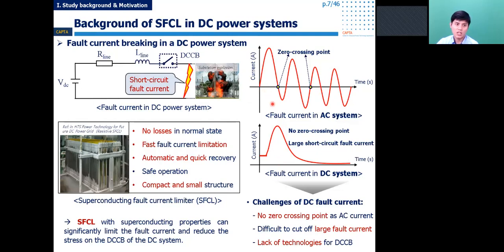About the background of the SFCL in the DC power system. Unlike the AC system, in the DC system the current does not have a zero crossing point, so it is very difficult for a conventional circuit breaker to cut off the short circuit fault current. Therefore, a current limiting device is required to limit the DC fault current to a relatively low level. A superconducting fault current limiter, with its superconducting property, can significantly limit the fault current and reduce the stress on the circuit breaker in the DC power system.